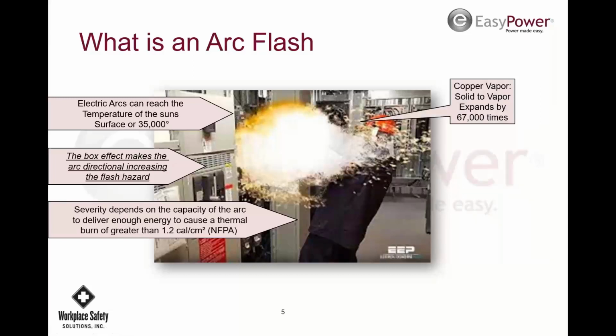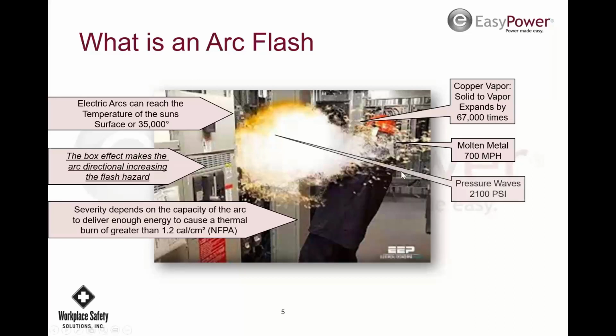Copper vapors expand 67,000 times. Now we're going to talk about the pressure. Molten metal travels out at 700 miles an hour. So even though our arc flash boundary may be here, doesn't mean the molten metal stops. It still keeps going. So you may do a risk assessment and say, I'm going to put a shield on anyway. Pressure waves can be 2,100 pounds per square inch. That's why you have all this molten metal. And sound waves, 140 decibels.